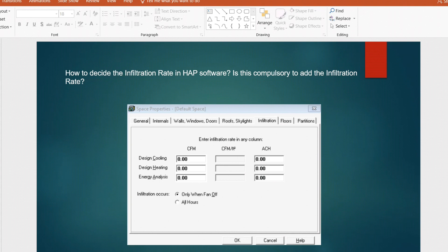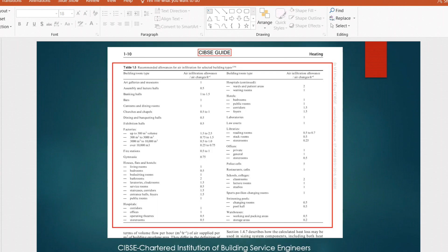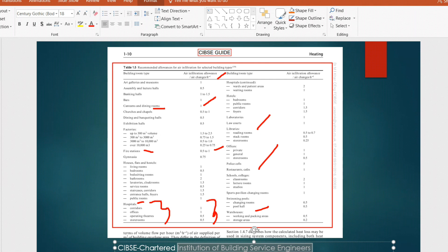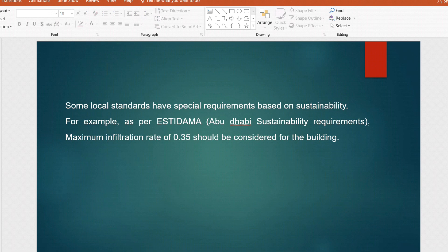Let's see some international standard requirements. For the standard reference, you can refer to CIBSE — the Chartered Institution of Building Services Engineers. In this reference you can see different air changes per hour for different buildings. For example, for canteens and dining rooms the air change per hour is normally one, for fire stations 0.5 to 1, and for hospitals different rooms have different values. Warehouses, industrial projects, restaurants, and libraries are also clearly listed.